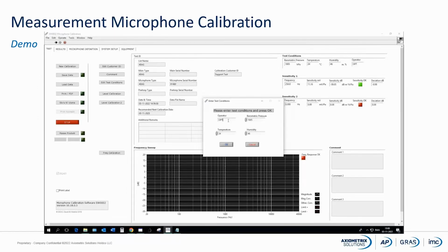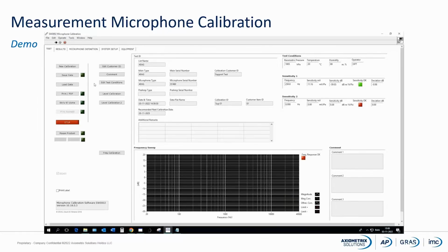When we start the microphone calibration system, then as with all other systems, we have to tell the system who is the user. The system will automatically read the barometric pressure from the piston phone. So we put in the reference conditions, the temperature, and the humidity. When this is done, we are ready to start a calibration. So we can click on the new calibration button.